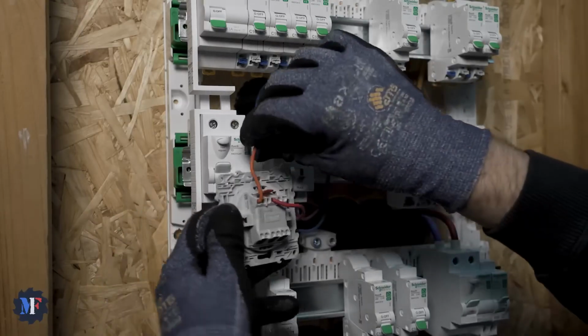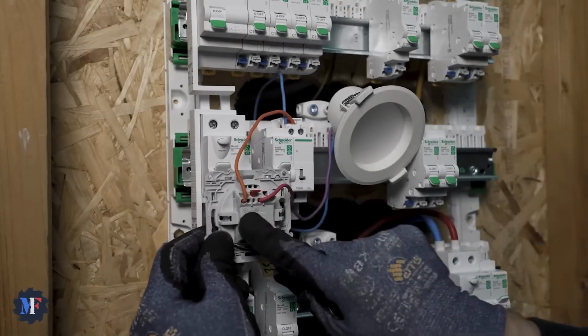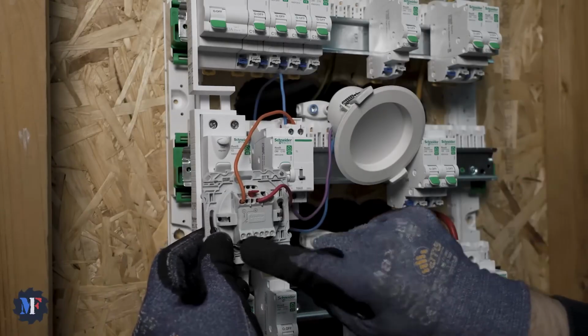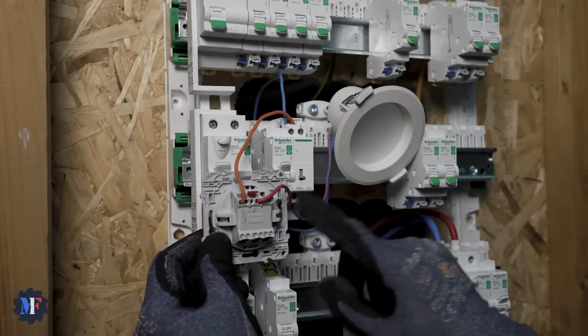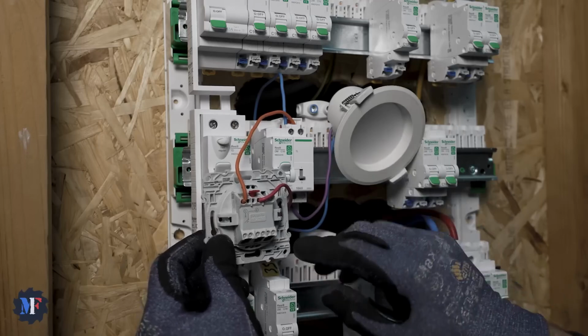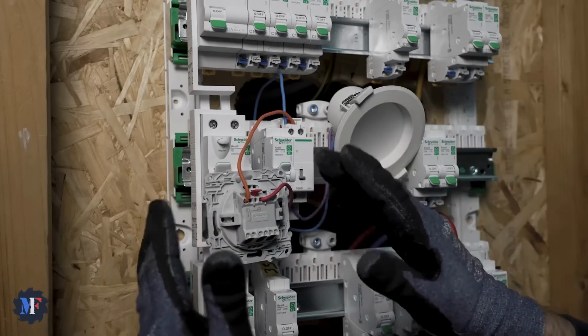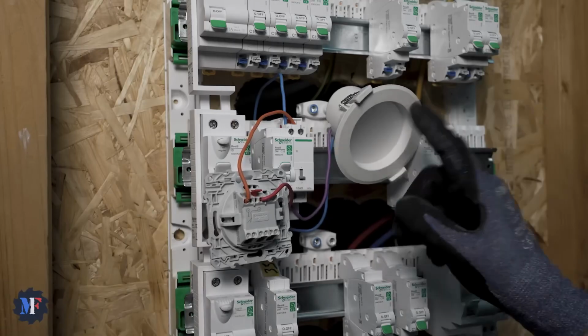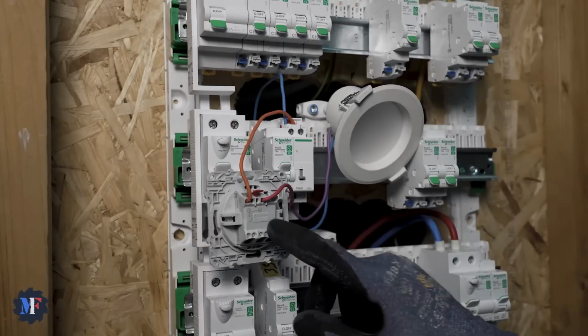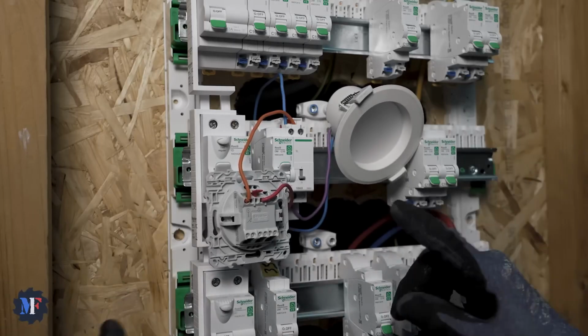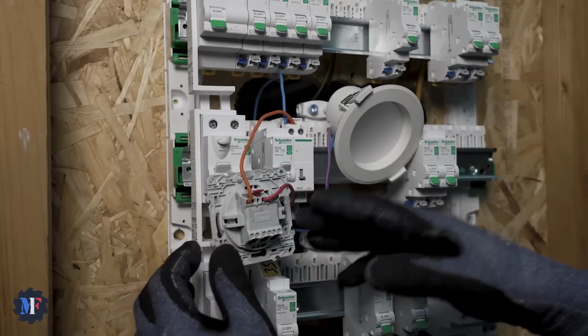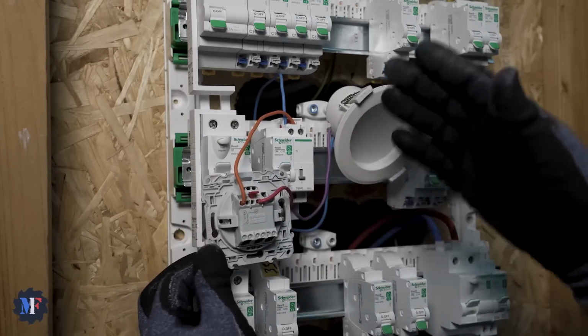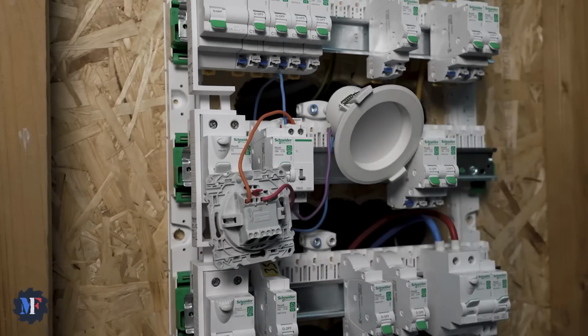Now, to add more, it's not complicated. We tap into terminal 1 and the phase terminal to power the other push buttons. But whether it's the push button or the light point, the best thing is to bring everything into one box, because if one day you decide to remove a light point or a push button, at least you won't cut off the rest. It's that simple. Why make bridges between them? If I have 3 push buttons and remove the middle one, the third loses power.